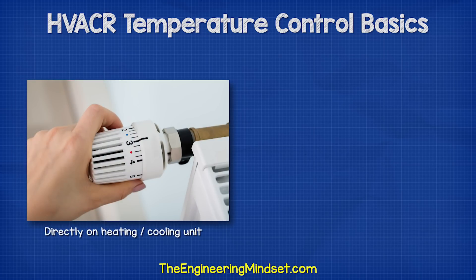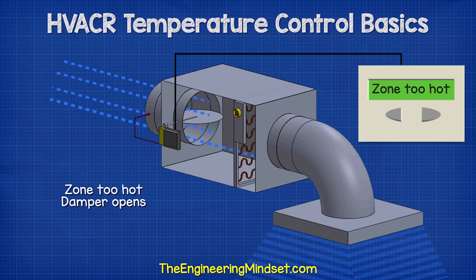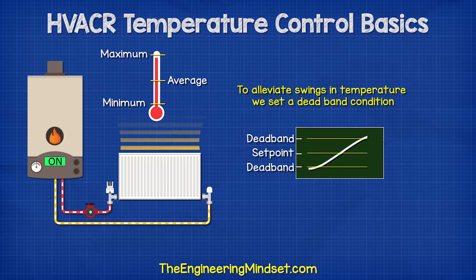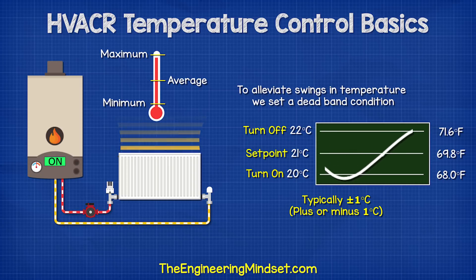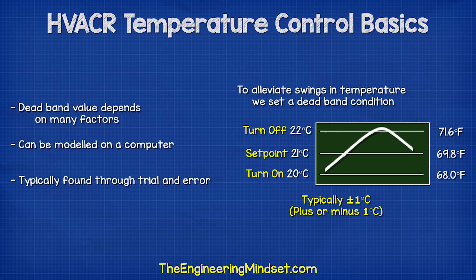The thermostat could be located on the output device, like a thermostatic radiator valve, or remotely, like a room thermostat which controls the position of a damper in a fan coil unit. To alleviate swings in temperature, we set a deadband condition, typically plus or minus 1 degree Celsius from the required temperature. For example, if we want a room temperature of 21 degrees Celsius, with a deadband of plus or minus 1 degree, the heating will turn on when the room temperature falls below 20 degrees Celsius and switch off when it is above 22 degrees Celsius, giving us an average temperature of 21 degrees Celsius. The deadband value depends on many factors — it can be modelled on a computer, but generally it is found through trial and error with small incremental changes to find the optimal point where the room is comfortable and the system operates efficiently.